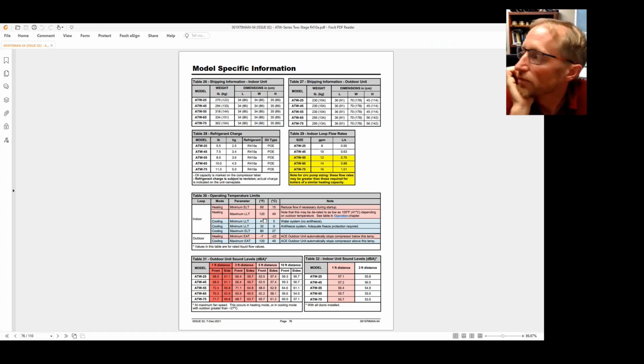Okay. And then is there a kind of rule of thumb in terms of transferring it to the buffer tank, what you'd end up storing the tank at? The water temperature set points for the buffer tank are in the settings of the heat pump. So in the control board, it won't let you set the temperature lower than the heat pump can achieve. And I can't remember exactly what the limit on that is. I think the minimum might be 40 to 42 anyway. I have to check on that, but the official specification here is that 41 is the minimum. So 40 would be a very reasonable setting.